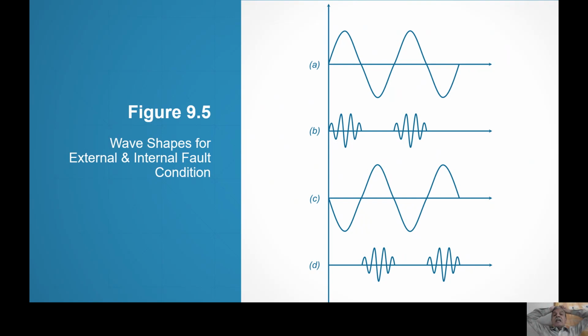Similarly, at B, from A to B it is transmitted. So at both the ends, the carrier modulated signal is available. And because it is available and it is a blocking scheme, only if the carrier is not available will tripping occur. Here tripping will not occur because the fault is not there or it is an external fault. Therefore, tripping will not occur.